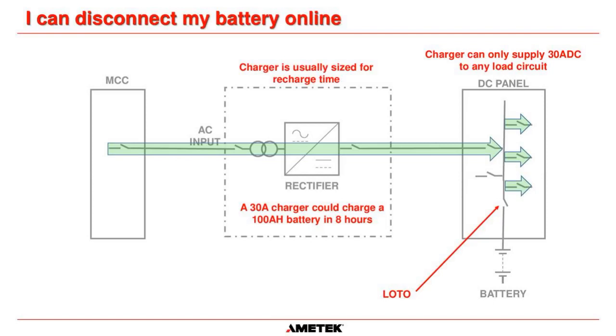In most cases, the charger will go into current limit of some form. And remember what I said, the only way we can limit the current is by reducing the voltage. So in most cases, when you put a fully discharged battery back online, the charger will go into current limit. Therefore, I can't tell you, Bill, what the voltage is going to be, but it's going to be above 105, obviously. But if the charger has been fully sized, then it could, in theory, go straight to 135 volts DC.